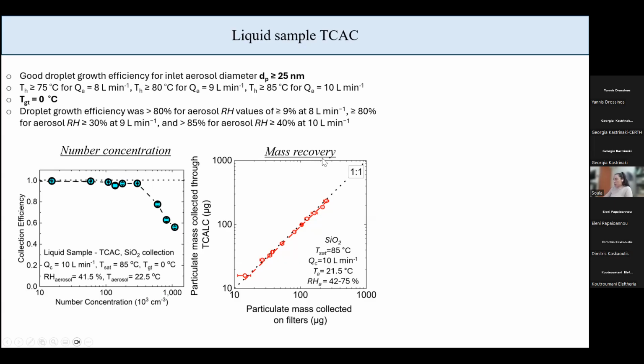And the next plot shows the mass recovery. It was obtained by doing the following experiment. I had one line where the liquid sampler, TCAC, was collecting sample at 10 liters per minute. And in parallel, I had a 37 mm particulate filter collecting the same sample at 10 liters per minute. So on the x-axis is the mass that was collected on the filter, and on the y-axis is the mass that was collected on the liquid sampler. This mass was first extracted on a filter through vacuum filtration, and then I used the mass balance to obtain the weight of it. And this is the correlation of these two techniques.